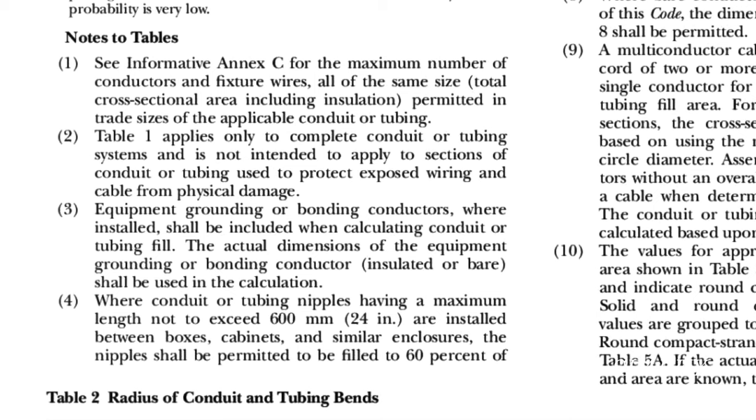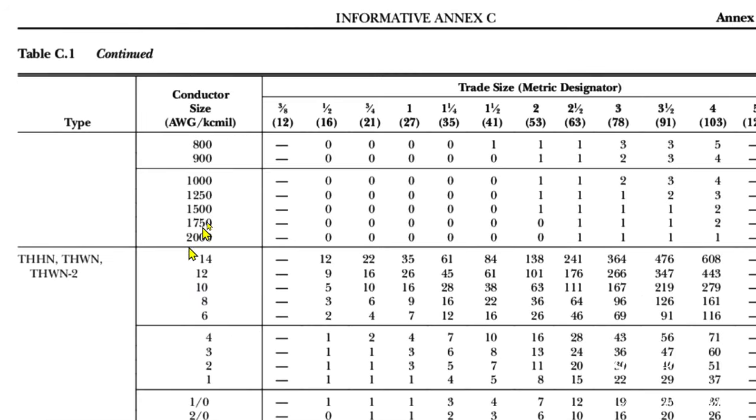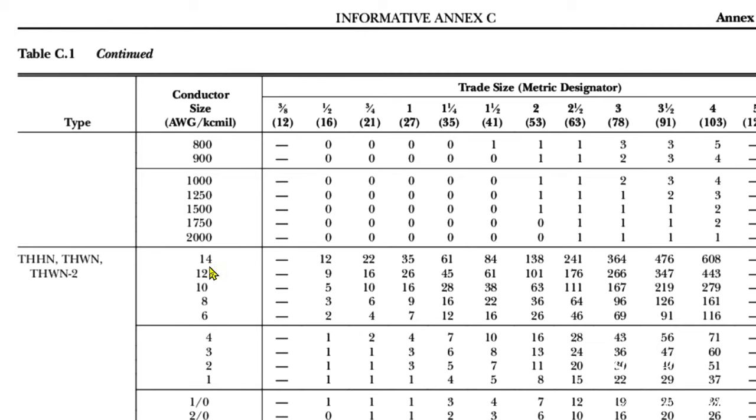So let's see if that number of conductors is permissible in half-inch EMT. So here we are at Informative Annex C. It can be found in the back of your code book, and this is for half-inch EMT right here. THHN—that's what we're using—and we see that we can put 12 14-gauge wires in half-inch EMT, or we can put nine 12-gauge wires in half-inch EMT. But we have eight 14-gauge and two 12-gauge, so we have a mix.